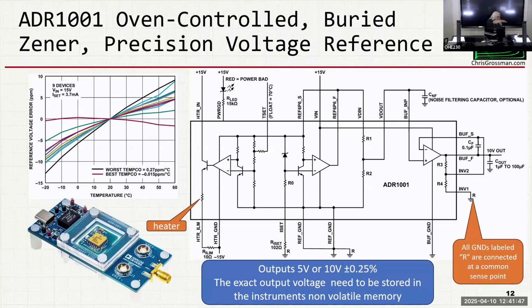Most instruments have a microprocessor in them now. So when they calibrate the instruments, they'll measure what that voltage is, and that gets put in non-volatile memory. If you change out that part and it dies, and you try to fix the instrument, it's not going to match. You'd have to recalibrate that part.